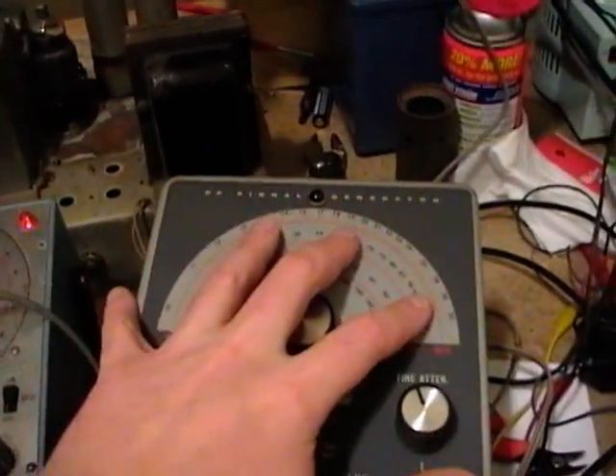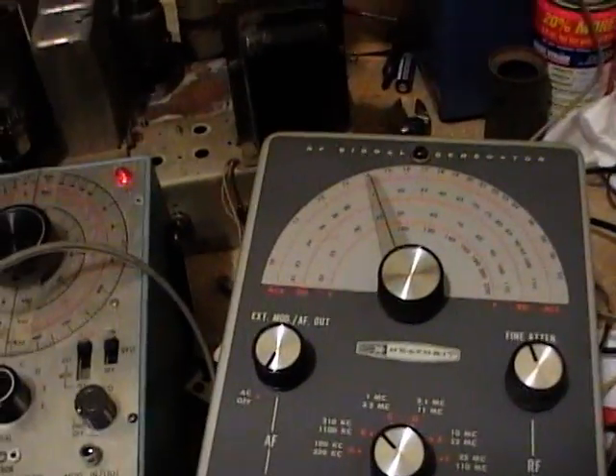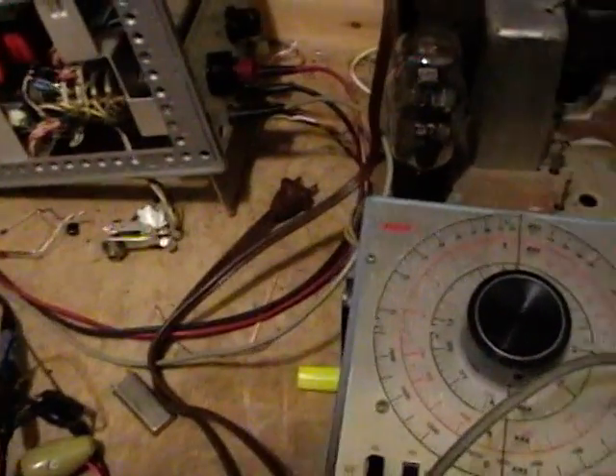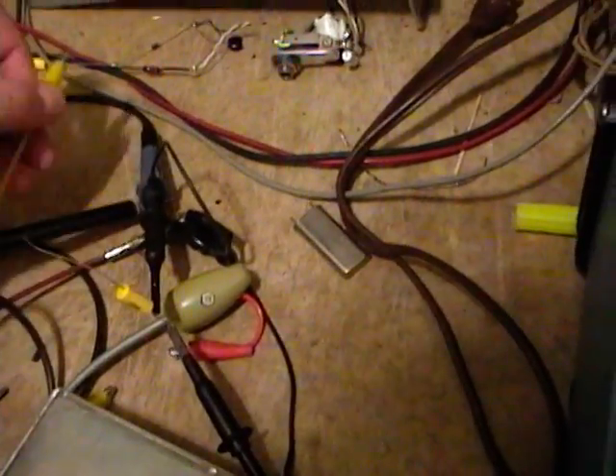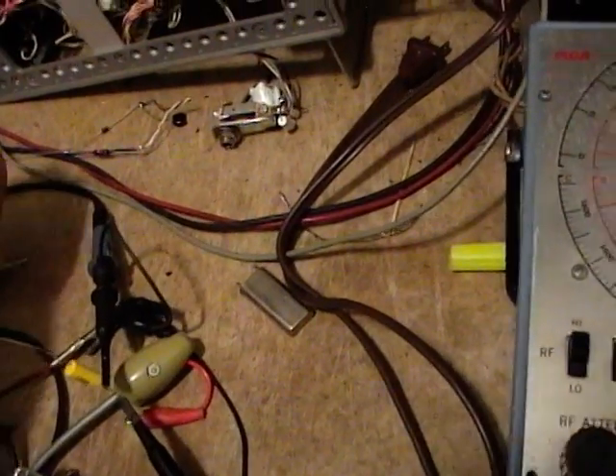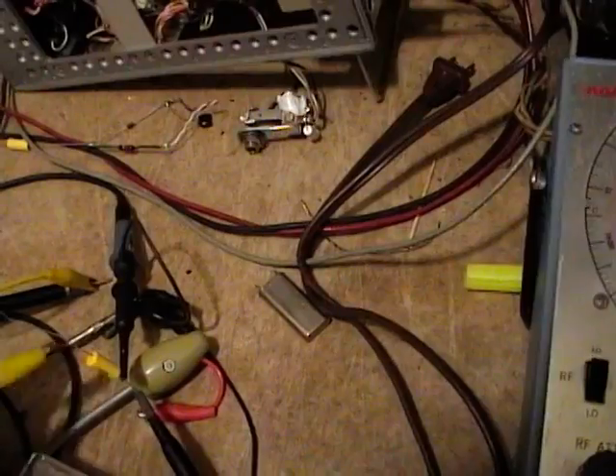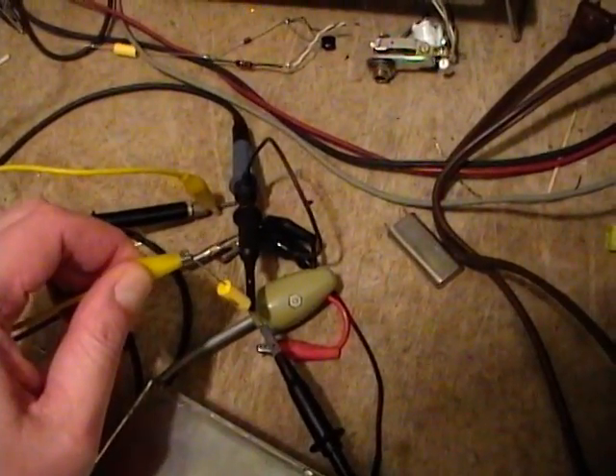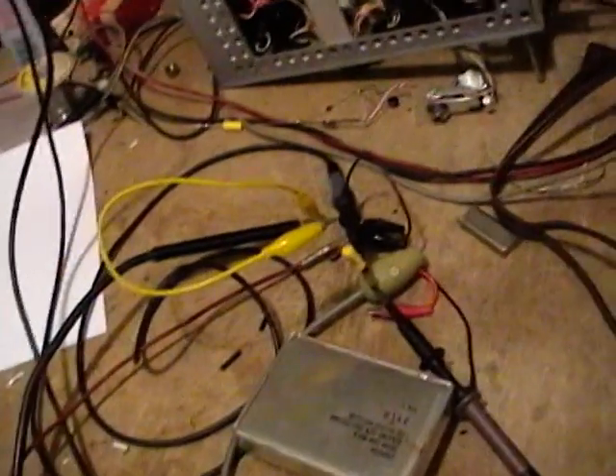Another way to do it is simply use a separate standalone RF signal generator and feed that in through a capacitor or a similar device. You don't want to directly short the two RF generator outputs together. And the two signals will mix, and you'll see a peak where the two frequencies are the same because it'll be like additive interference. You ever took physics when you learned about when water waves hit each other and you get peaks and troughs and all that? Well, when the two frequencies, in other words the swept frequency equals the marker frequency, you get a boost in the amplitude and you get a blip on the screen. Or on the scope, I should say.